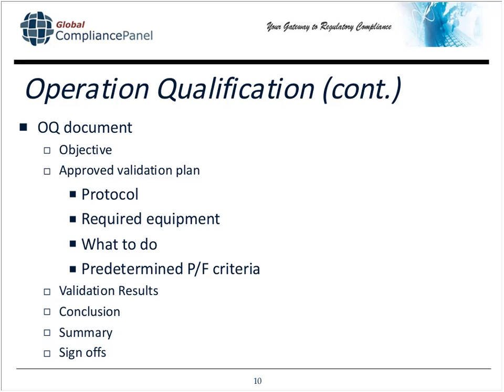When you include a summary in your OQ and other technical documents as well, it enables the reviewer to look at that summary, which is written for a layperson, and understand it, and then it gives them a good starting point to go into the OQ, because they will go into the OQs that they review page by page and test by test. So it gives them an idea of what it is that they're seeing. Putting raw data in front of a reviewer, whether it's your notified body or FDA or OEM partner, is just asking for a lot of confusion.